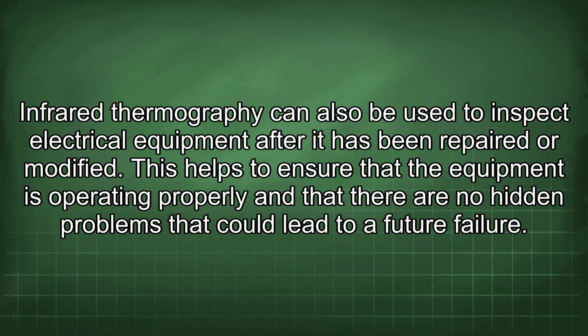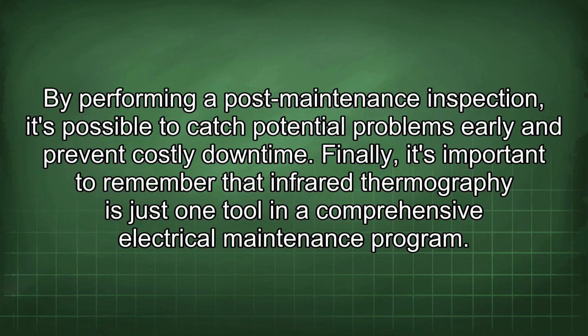Infrared thermography can also be used to inspect electrical equipment after it has been repaired or modified. This helps to ensure that the equipment is operating properly and that there are no hidden problems that could lead to a future failure. By performing a post-maintenance inspection, it's possible to catch potential problems early and prevent costly downtime.